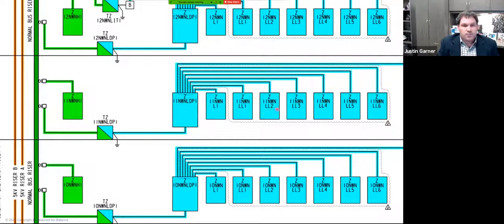And panel boards are most like what you would recognize in your home that distributes power within your home or another light commercial facility. These are intended to get down to branch circuits, as we call them. Your typical 15, 20, 30 amp branch circuits that would feed lighting and plugs and much smaller loads, whereas your distribution panels will typically feed higher amperage loads.